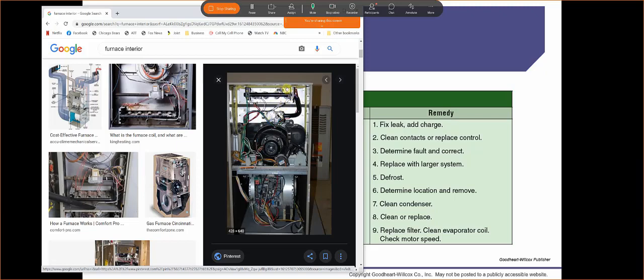So our hot surface igniter is going to warm up. Once it warms up for a certain amount of time, it could be 10 seconds, 15, whatever the manufacturer dictates. This gas valve right here is going to energize. It's going to send gas through the black tube and shoot it into the heat exchanger. It's going to start warming up this heat exchanger, making it nice and hot.